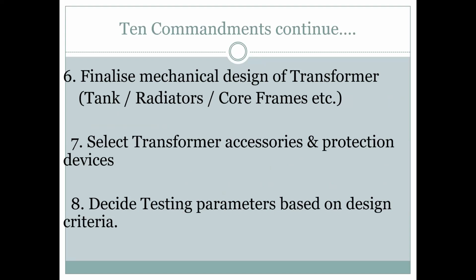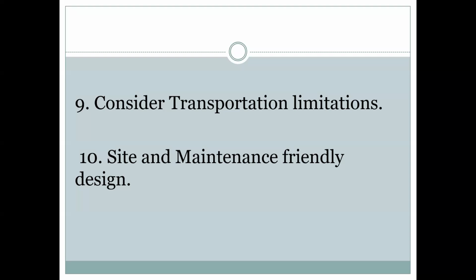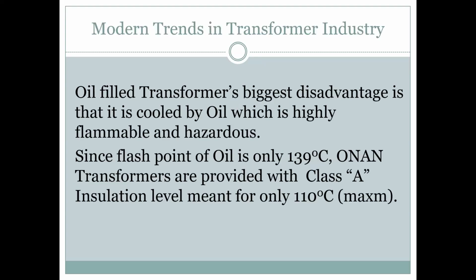Then finally, mechanical design: tank, radiators, core, all these things. The transformer accessories and protection devices are also there, like OTI, WTI, all these things. Decide testing parameters based on design criteria. Next, quickly. Here you also have to keep in mind the transportation limitation. Our transportation is limited by tonnage. So we always have to remember that after dismantling, the transport weight should not be more than the permissible transportation weight. The site and maintenance can be designed so that it is easier to access all these accessories.